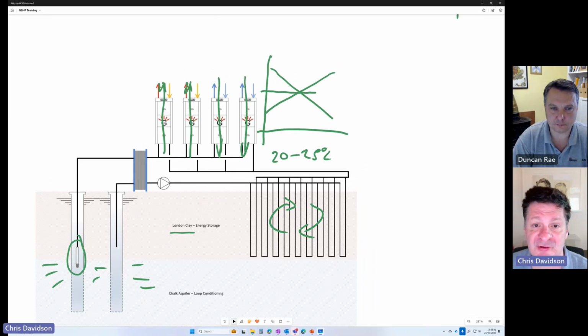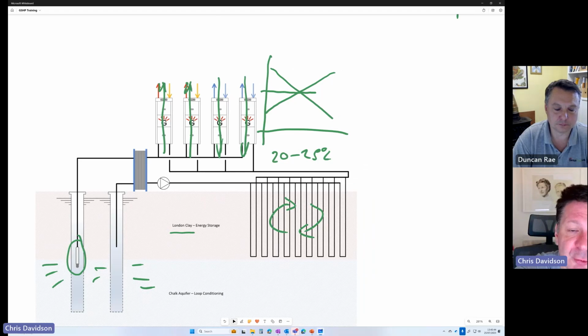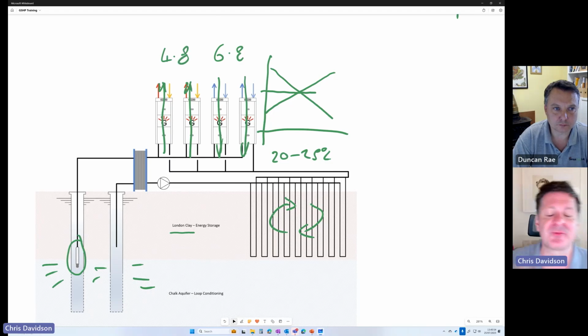Last time I saw some numbers on this system, we were achieving a seasonal coefficient of performance. So, how much energy do we get delivered divided by the electrical consumption? We were getting 6.8 in cooling and 4.8 in heating. So very, very high efficiency systems.